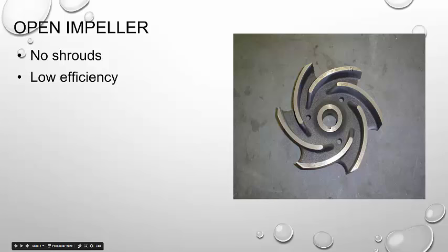Which is what draws the water in. High pressure out on the edges of these vanes as my volute gets bigger. Remember there's a big play between velocity and pressure. So high pressure here on the edge, low pressure here. If this whole thing is open and I have water coming out here in the high pressure zone, there's a good chance for that water to make itself back down into the low pressure, and then I'm re-pumping the same water.